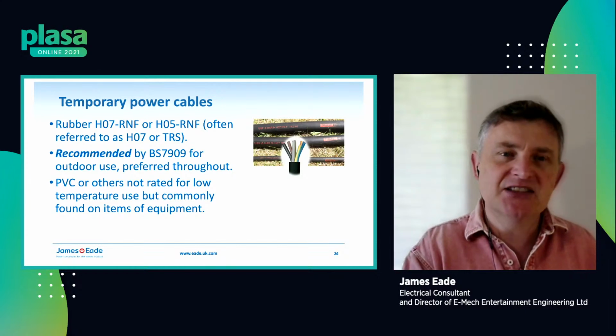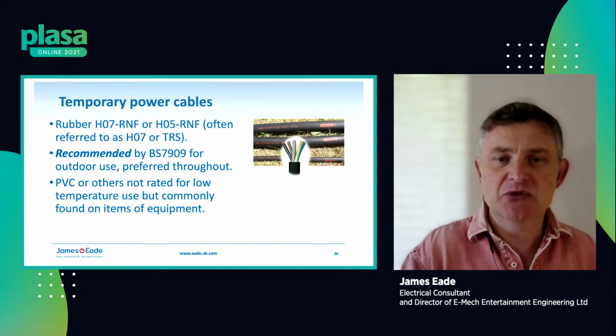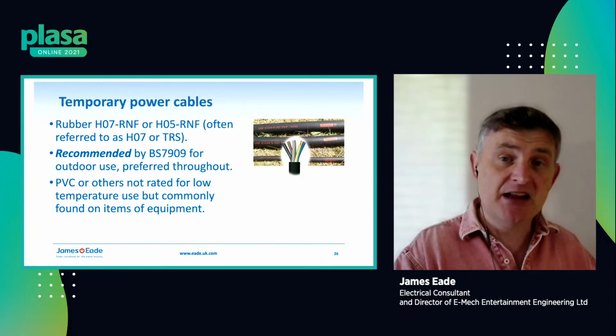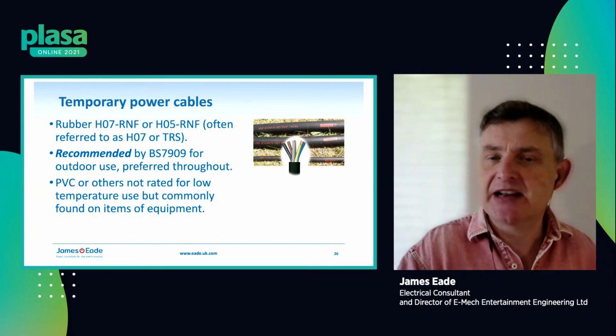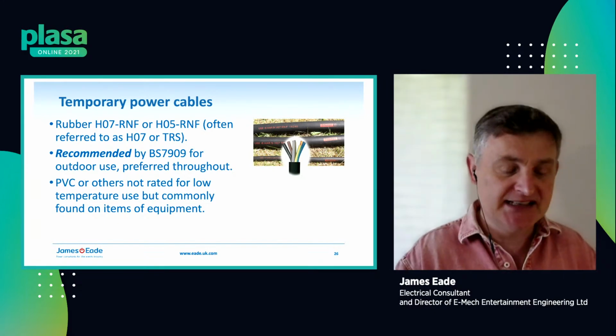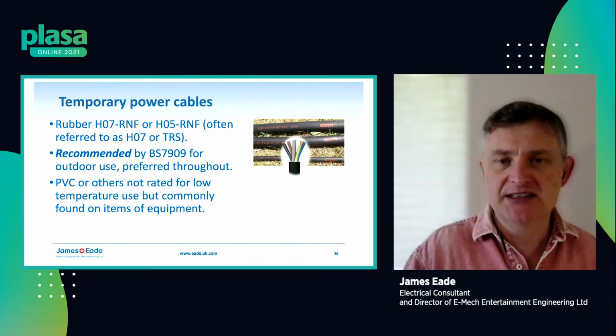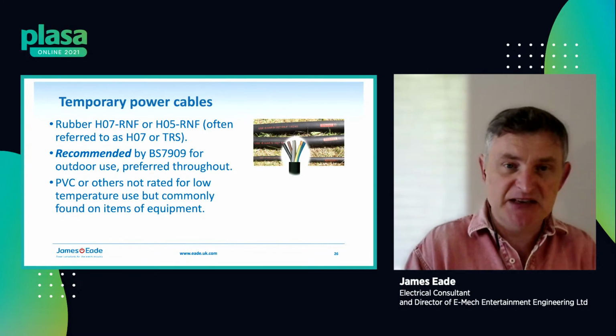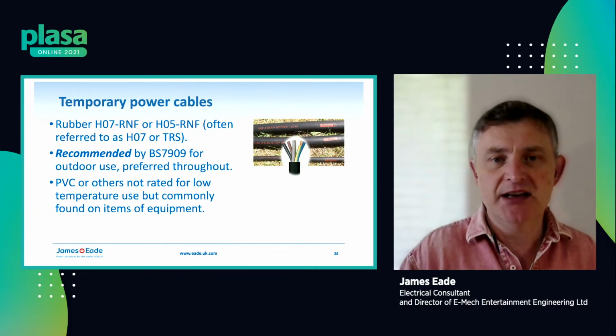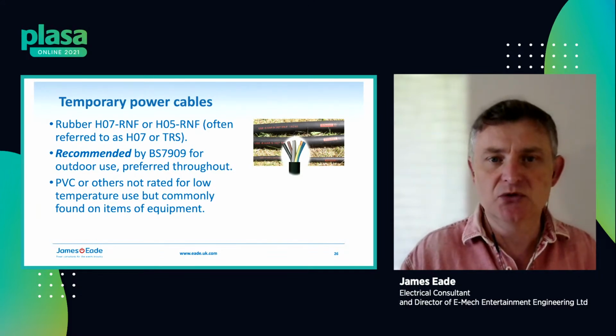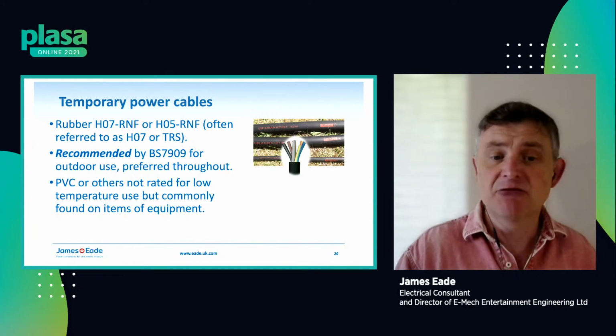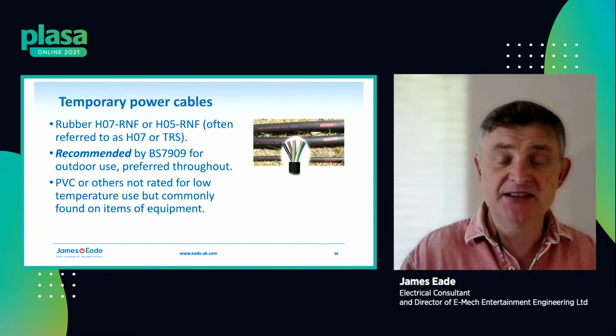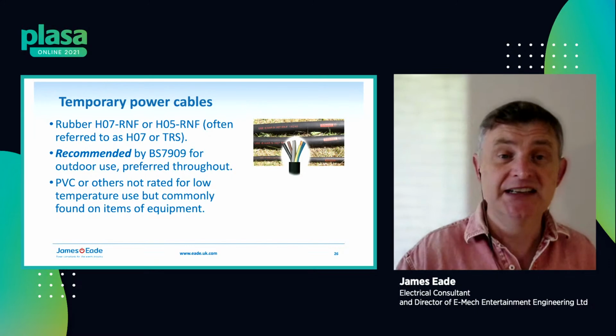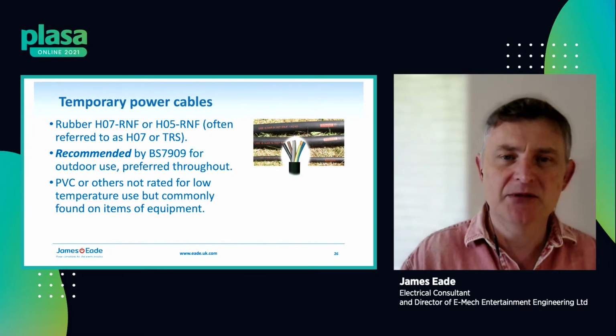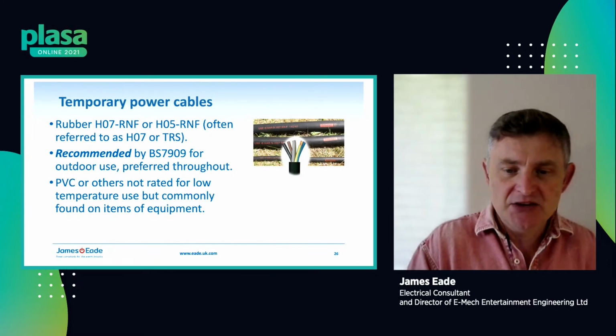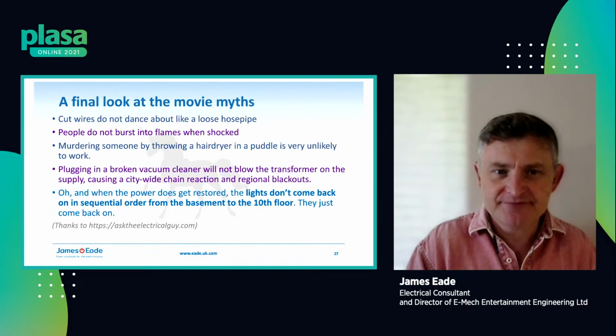It doesn't ban the use of plastic cables, but just when using plastic, be very aware of the likelihood of mechanical damage. And it's very easy to see on blue Arctic extension leads where you can see the insulation's been scuffed and cut away, just being dragged across floors and sharp edges. So rubber, very much the answer for that. And also it works a lot better outside in the cold than plastic does, a lot easier to coil up at the end of the gig. So I think one more slide.